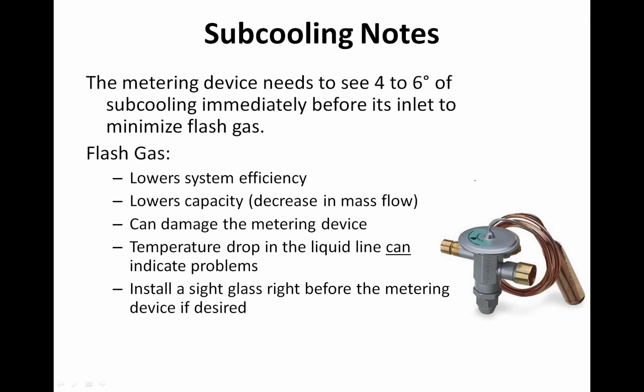And temperature drop in that liquid line can indicate problems. So typically, a really easy thing to do is to measure the temperature of the liquid leaving the condenser, and then measure the temperature again where it enters the metering device. If you have a liquid line drop much over 3 to 4 degrees, it could indicate that you have an undersized liquid line and you're actually having some problems there. Now, obviously, you could be running across a hot roof, or you could be running through a cold area and also cause changes in liquid temperature. Barring those things, and obviously you'd have to take those into consideration, that's why it can indicate a problem. That's a thing you want to check.